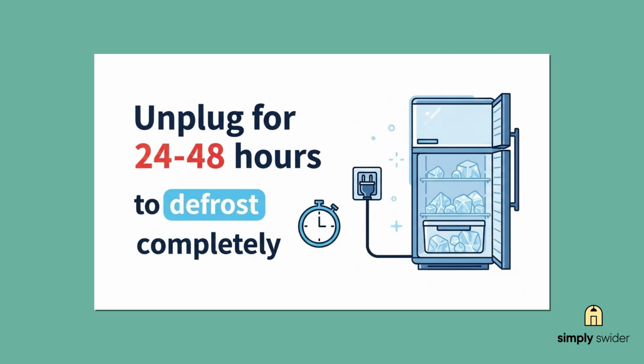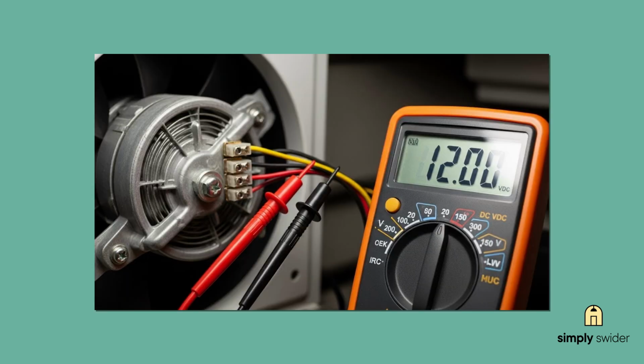Once it's thawed, check the wiring harness between the fan and control board. Look for any damaged or loose connections. If the wiring looks good, grab your multimeter and check for 12 volts DC between the red and brown wires going to the fan motor. If you've got power but the fan still won't spin, that motor's shot and needs replacing.